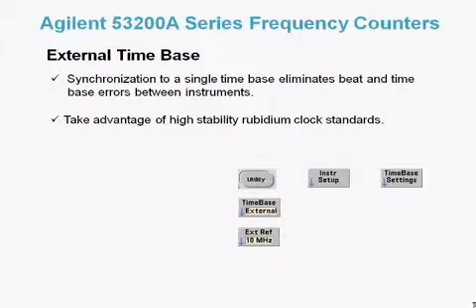One of the advantages of using an external time base is that synchronization to a single time base eliminates beat and time base errors between instruments. Another advantage is the ability to take advantage of high-stability rubidium clocks that are available on the market.